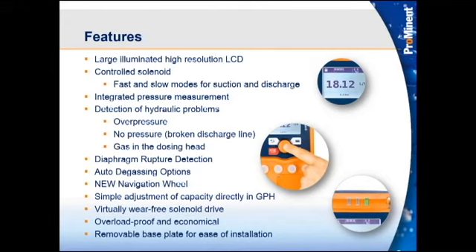That could mean that there's potentially a broken line somewhere, and that reduction in energy would be recognized as a P minus error on the pump. Okay. Next, you see the detection of hydraulic problems. I mentioned the overpressure, the no pressure. We also are able to detect any gas in the head. So if we're pulling in any air through the line, the pump will recognize that and try to evacuate that air out of the head.